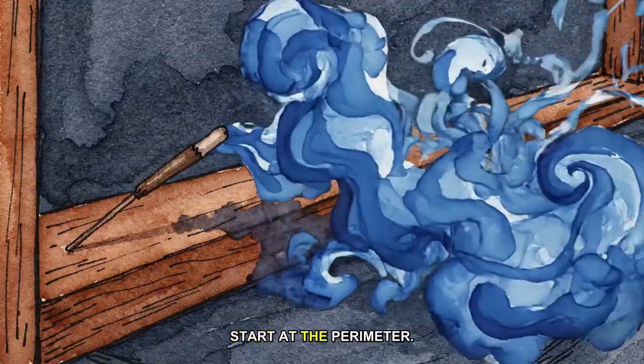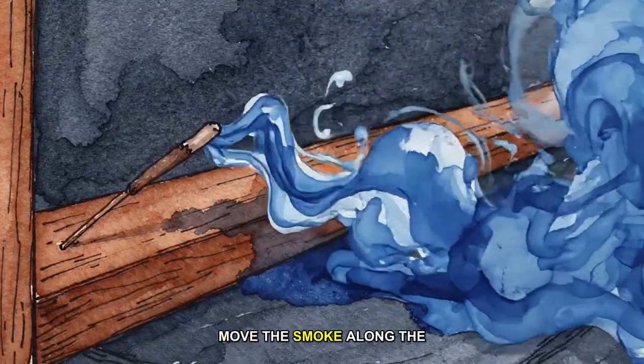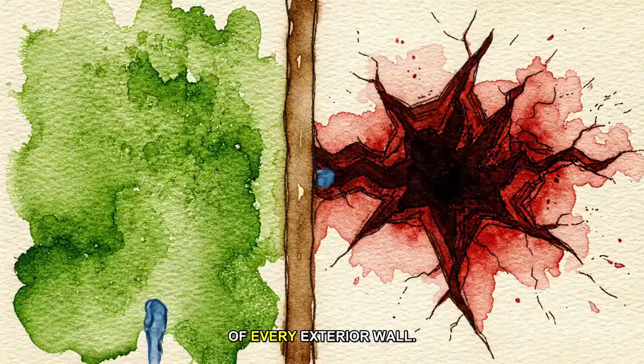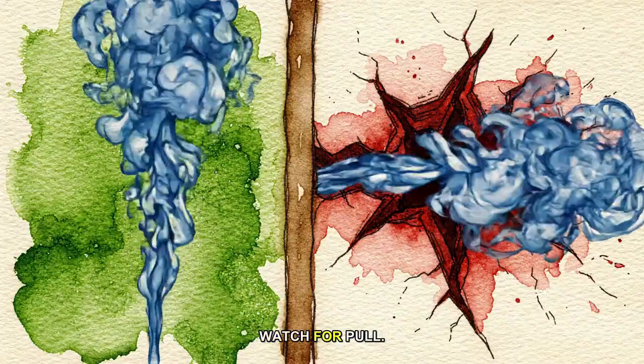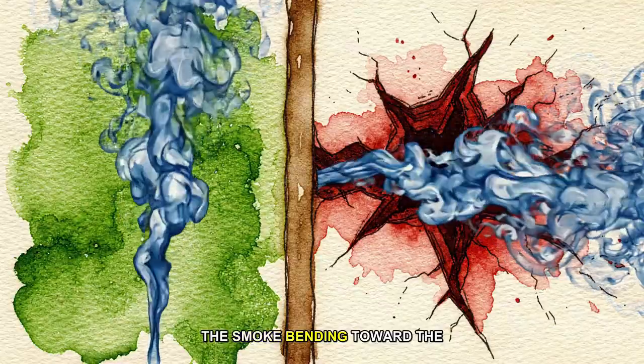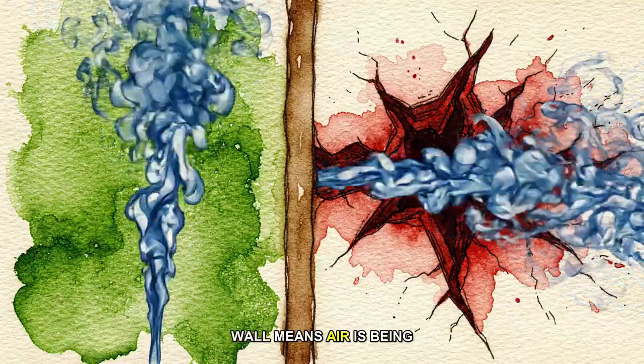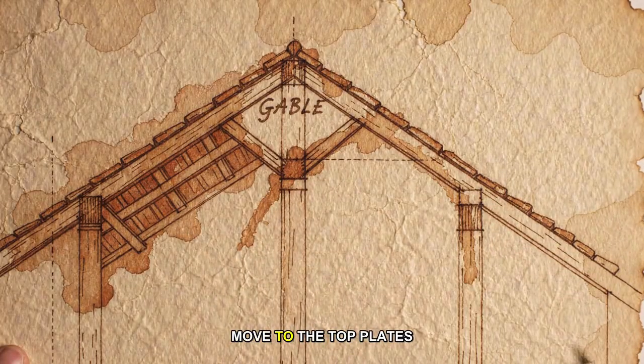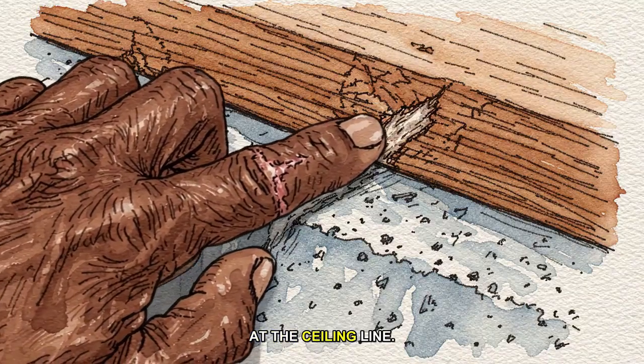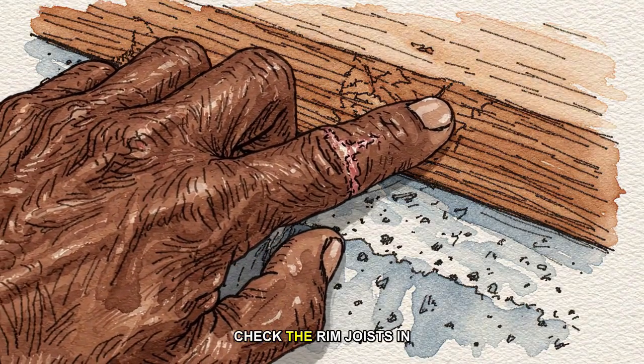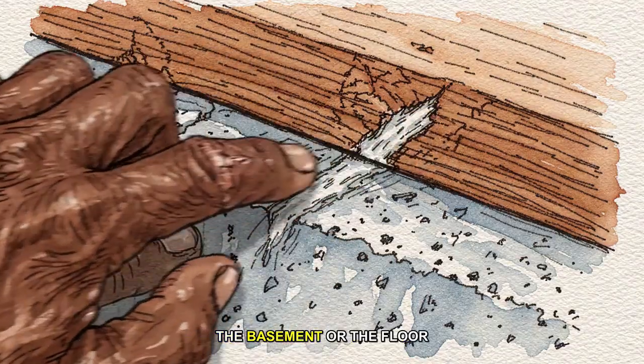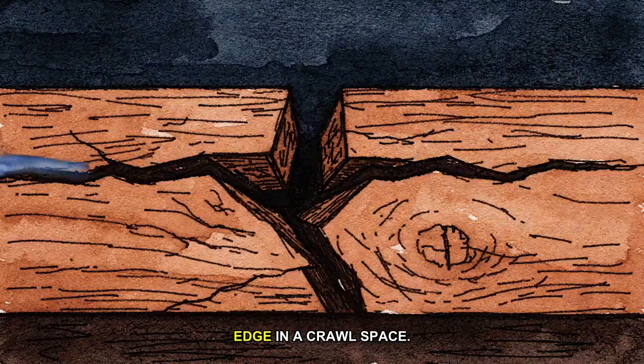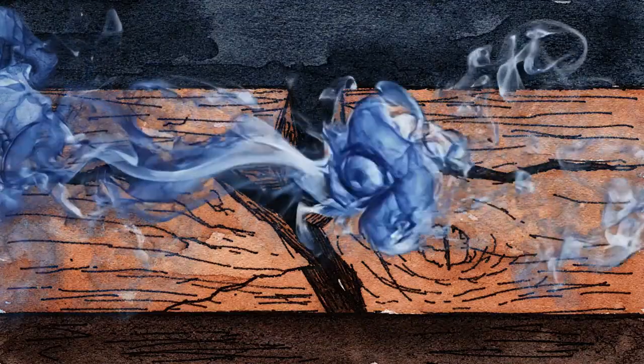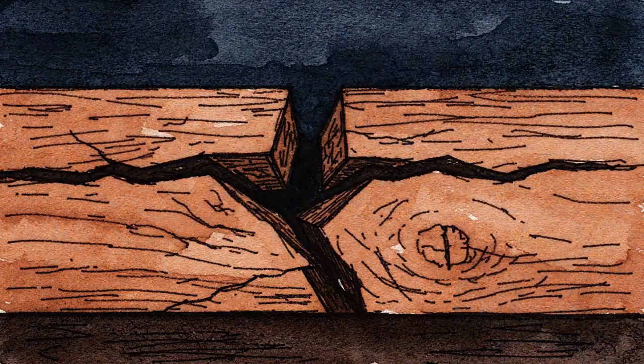Start at the perimeter. Move the smoke along the sill plate at the base of every exterior wall. Watch for pull. The smoke bending toward the wall means air is being drawn in. Move to the top plates at the ceiling line. Move to every electrical outlet and switch on exterior walls. Check the rim joists in the basement or the floor edge in a crawl space.